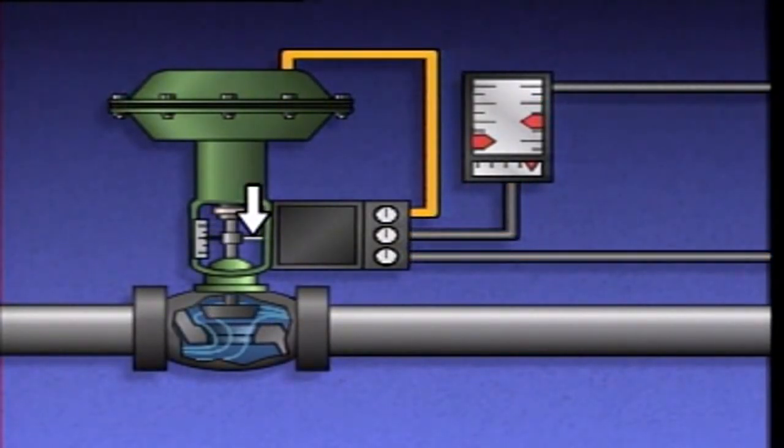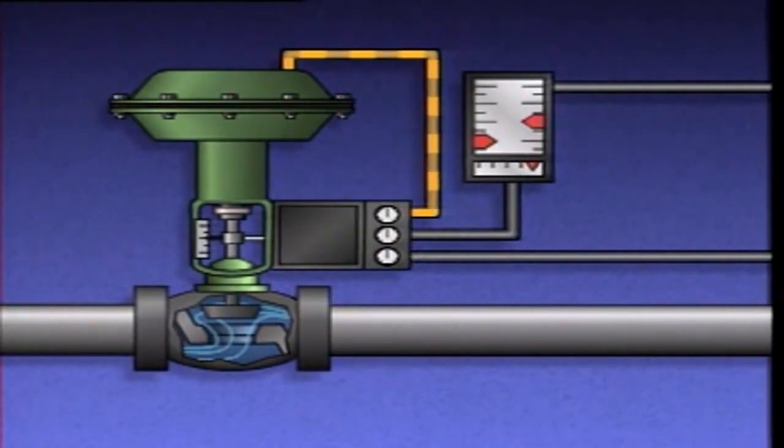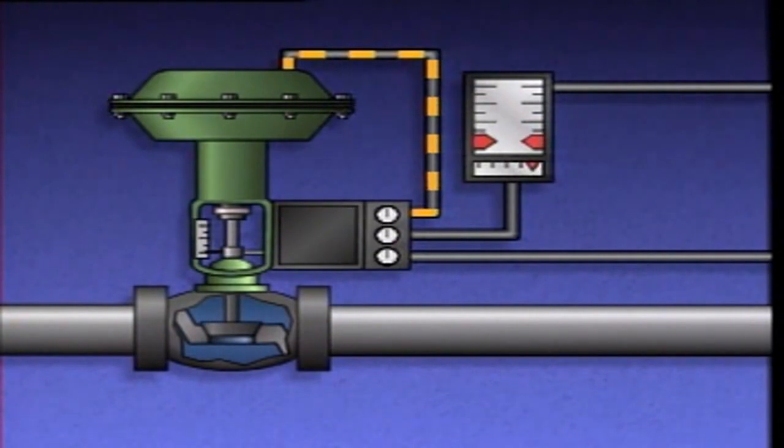The feedback linkage indicates to the positioner how far the valve is from the desired position, in this case fully closed. As the valve moves toward the fully closed position, the feedback linkage causes the positioner to change the air signal to the actuator, so that as the valve reaches the fully closed position, actuator movement is stopped.